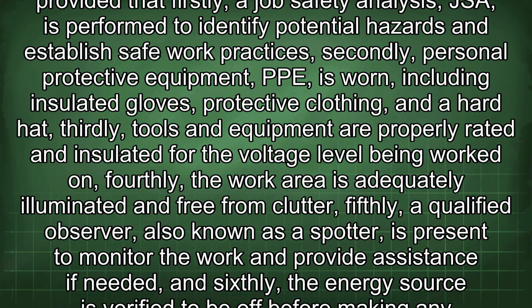NFPA 70 allows live work, including hot work, provided that: first, a job safety analysis (JSA) is performed to identify potential hazards and establish safe work practices; second, personal protective equipment (PPE) is worn, including insulated gloves, protective clothing, and a hard hat; third, tools and equipment are properly rated and insulated for the voltage level being worked on; fourth, the work area is adequately illuminated and free from clutter; fifth, a qualified observer, also known as a spotter, is present to monitor the work and provide assistance if needed; and sixth, the energy source is verified to be off before making any electrical connections or disconnections.